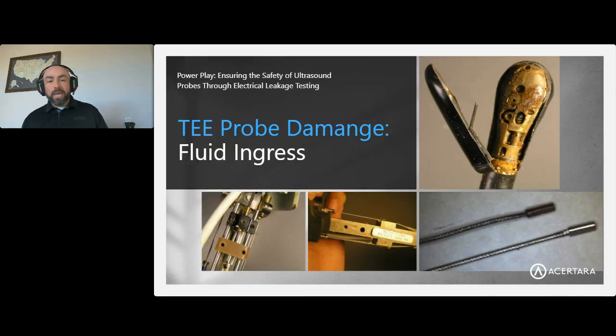So I've mentioned TEE probe damage, fluid ingress. What does that actually look like? You can see some of the rust and contamination forming inside this TEE probe tip. Many of these probes today have complex electronics, with high voltage switches called MUX chips. They might have application specific integrated circuits, ASICs, that are actually the whole brains of that particular ultrasound probe. The ultrasound system becomes more of a passive player in that transmission because it tells the probe go, and the ASIC is actually what creates the ultrasound, or forms the beam, gathers the transmit receive data, and then transmits complete data back to the ultrasound system. So these are very vulnerable to that fluid ingress.